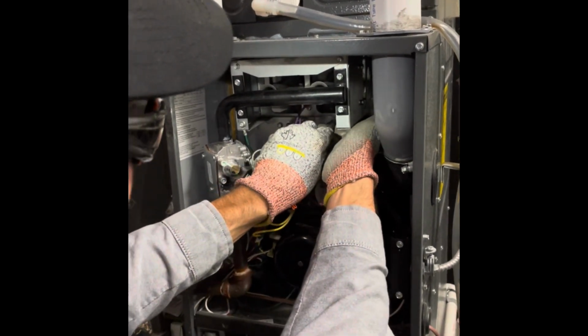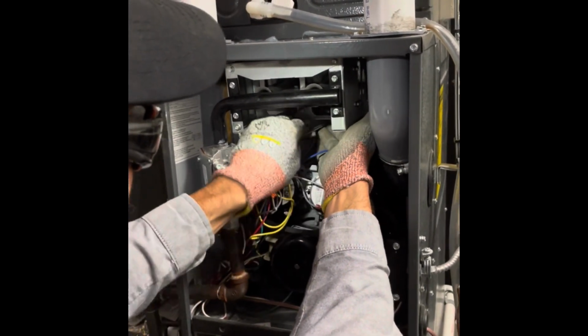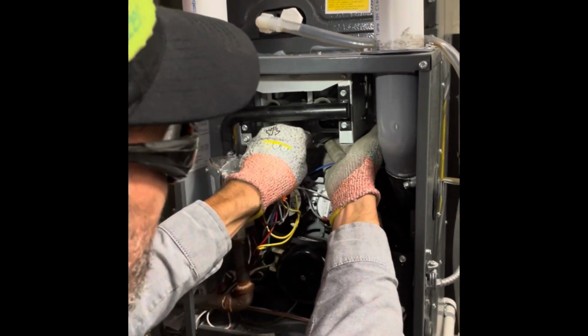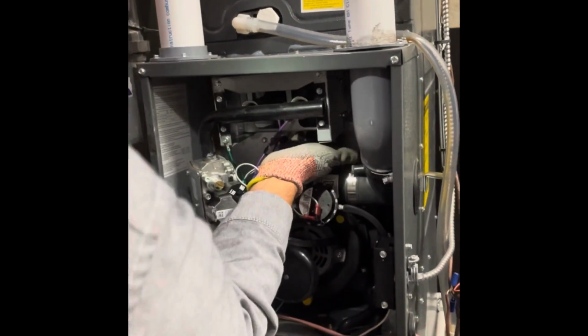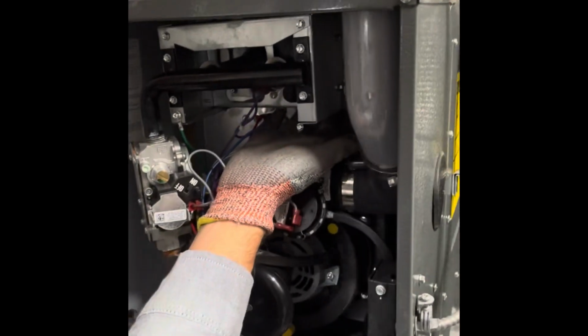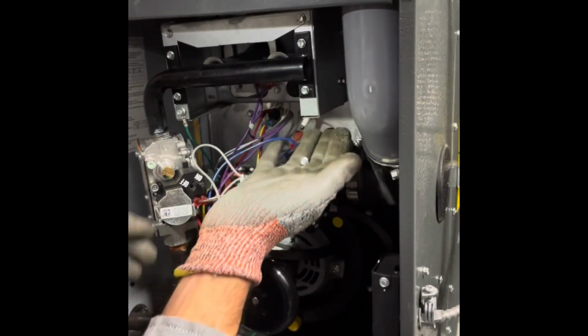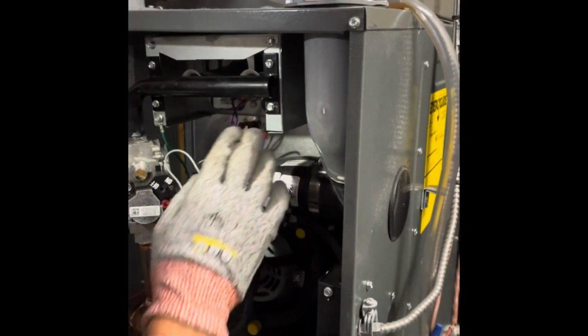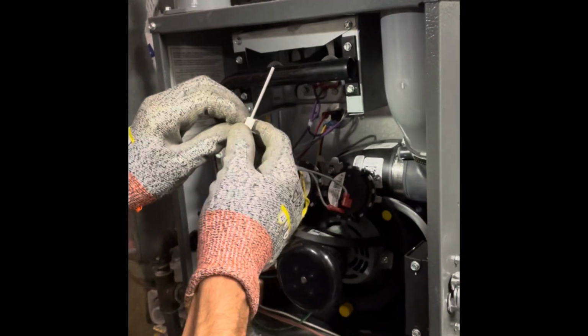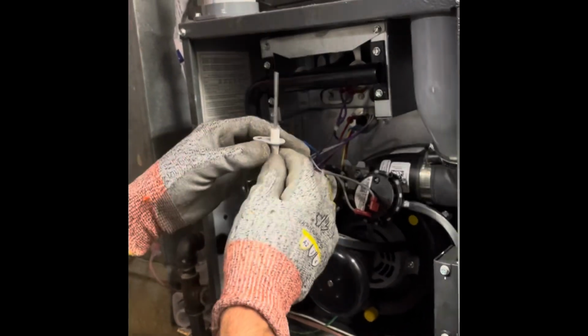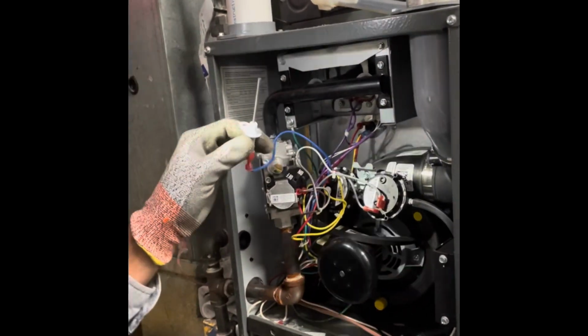Okay, so this sensor's almost out. Couple more turns and I should have it drop. There it is. You've got to be careful you don't drop that screw in behind everything, because you'll never get it back. So I'm going to place that there. Here's the flame rod. So soot buildup, carbon builds up on these. If they get very dark and dirty, they're going to prevent the furnace from heating up.